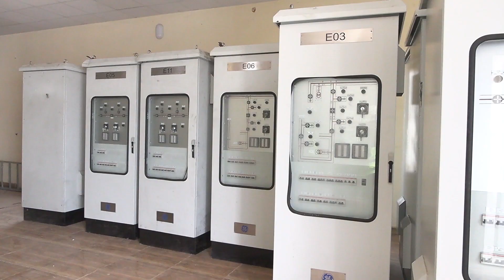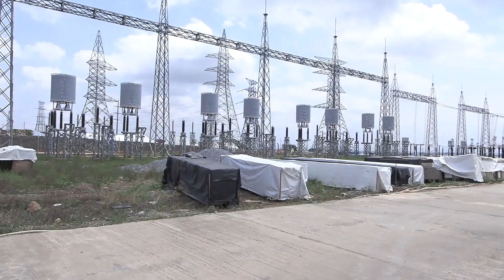There are more sets of equipment as part of the components of the substation, says the TCN official. This project has two 330 kV line bays coming from Gwagwalada. We also have 2x150 MVA power auto transformers, and 3x60 MVA power transformers with 9 33 kV feeders, and 4x132 kV line bays, which will be radiating power to Kukuaba and Kuje respectively. This project is sponsored by the French Development Agency (AFD), and is currently at 91% completion.